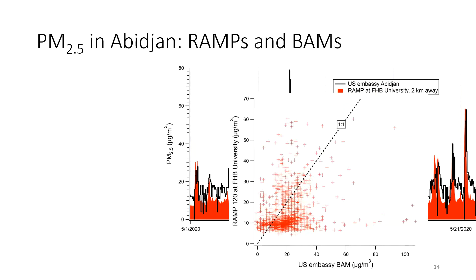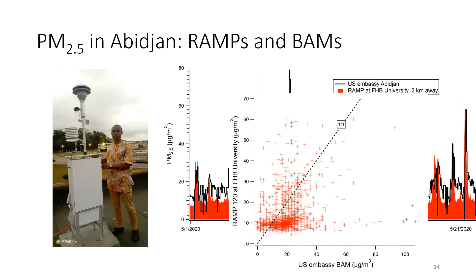And as of a couple of weeks ago, we have set up a BAM at the Felix Houphouët-Boigny University. And that's Dr. Julian Bahino after installing the BAM. And hopefully we will soon have a localized collocation-based calibration for the PM2.5 measurements in Abidjan. These are some recent data from Accra, Ghana, where we have a reference NOx analyzer. And we will be collocating RAMPs with the NOx analyzer for localized calibration of the RAMPs.